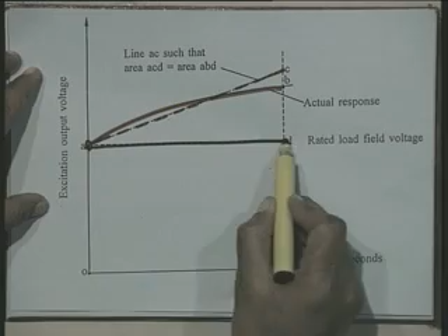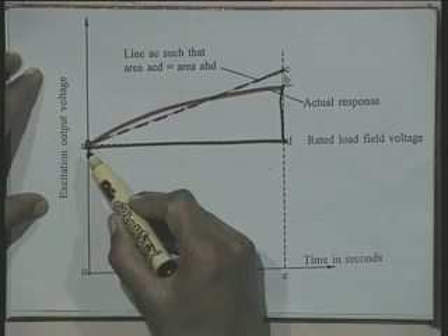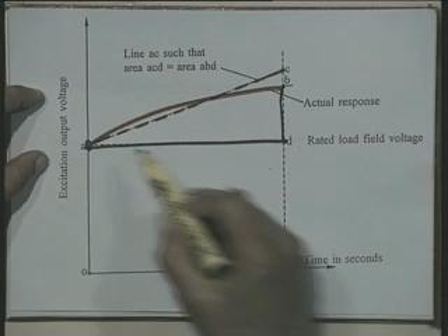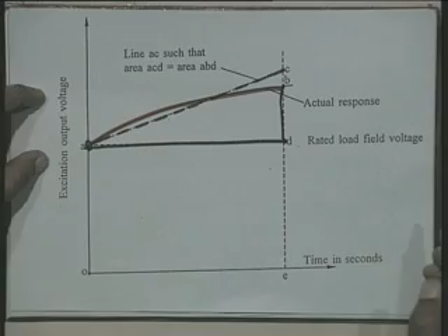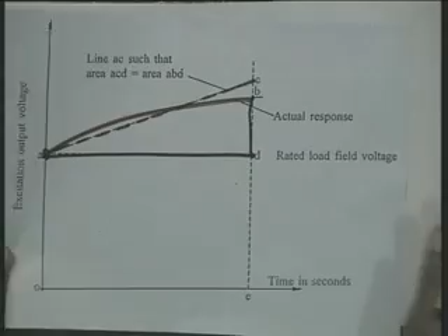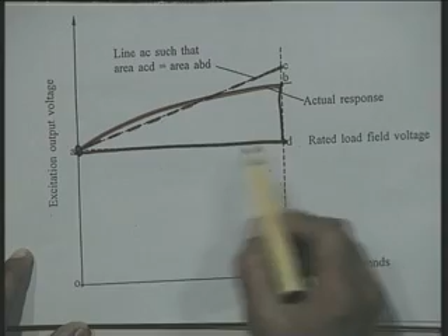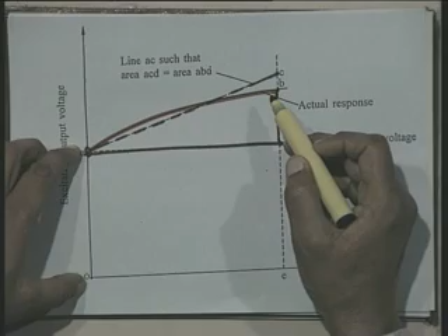This is the actual response curve. You draw a straight line such that this area ABD is equal to the area ACD, where ACD is the area of the triangle. Then the slope of this line represents the nominal response. The slope is CD divided by AD. You get this slope and divide it by the rated voltage, so that you get the nominal response. Now, there is a reason for choosing this time of 0.5 second for defining the nominal response.